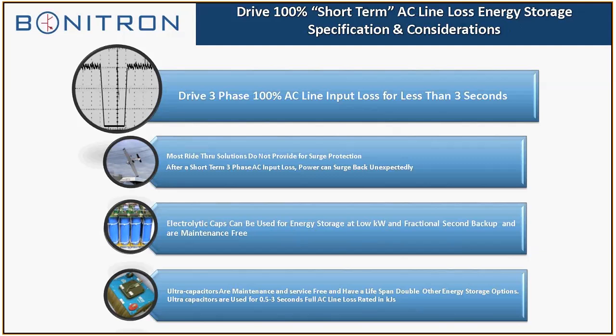And as I said, we've done a lot with electrolytic caps too. Depending on the drive, we have to know a little bit more about the drive to be able to use electrolytic caps by just putting electrolytic caps on the bus without the UPD ride-through. We can do that depending on the specification. We've done it a couple times this past year to where we just added bus capacitance. So if the customer's really budget conscious, they only need a little bit of ride-through, we can look at specifying just a cap bank and not having to add the chargers and the booster and all that.